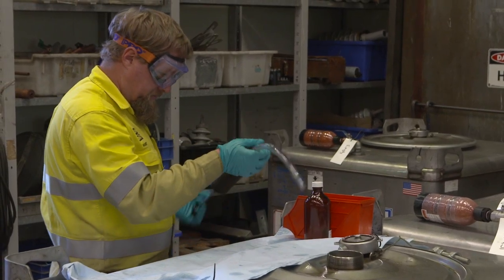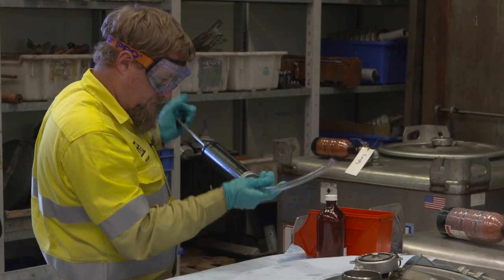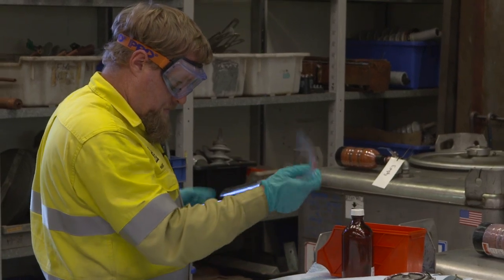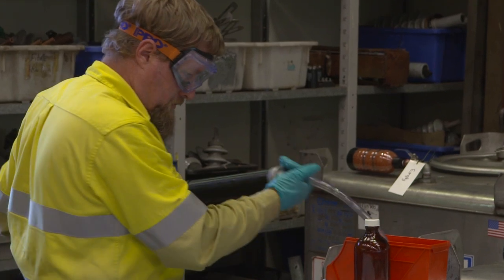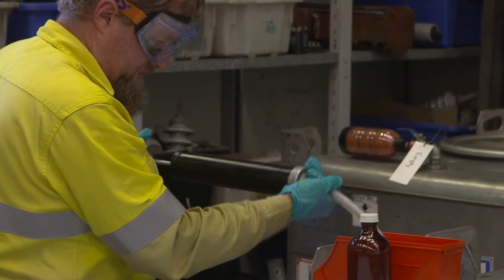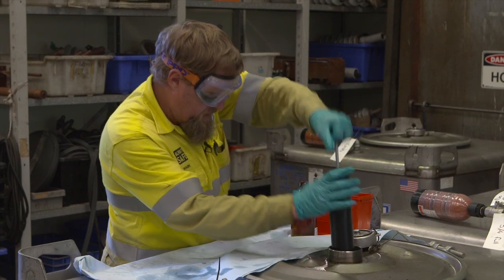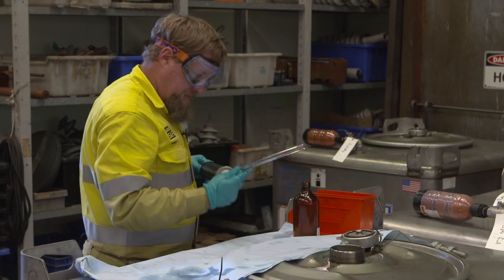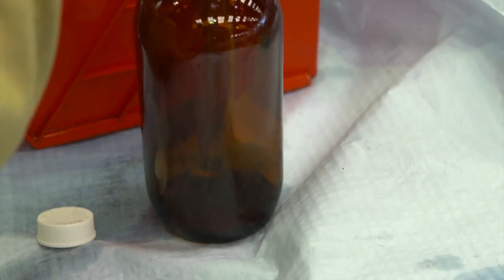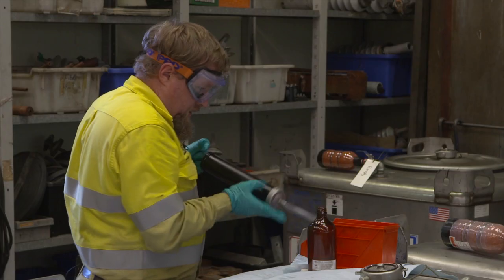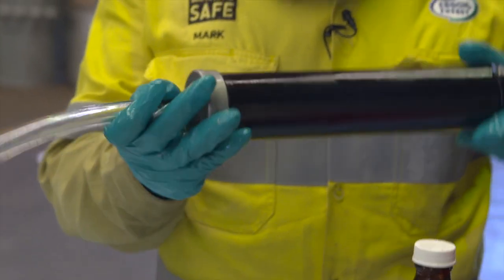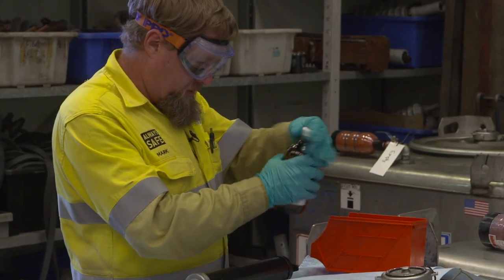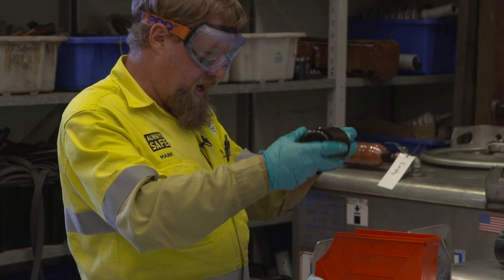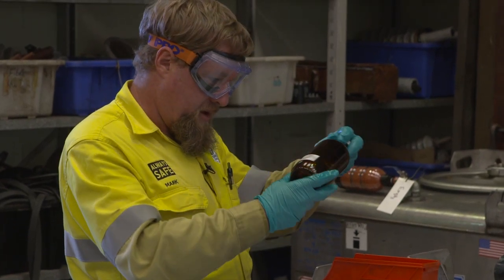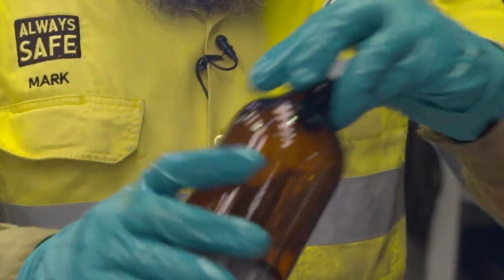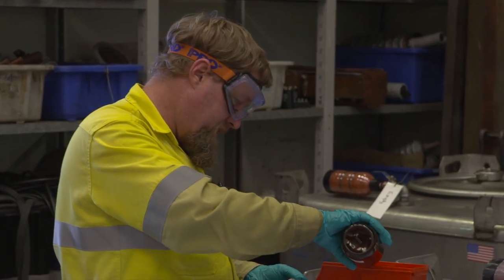Clean the syringe. And then discard the oil. Next, we want to flush our sample bottle. And with any leftover oil, give the syringe another clean. With the bottle, we want to put the lid back on and gently roll it around. So if there are any contaminants in the bottle, it should remove them. And then discard any oil.